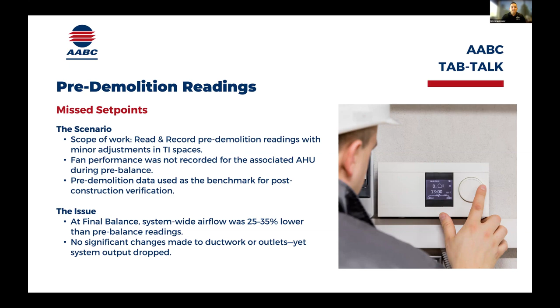This was kind of a follow-up to that, but we didn't have a baseline of the air handler, no RPMs or static to identify what it was doing at that time. So even though it looked like a simple read-and-record of the space, it turned into a bigger project, because now we're trying to reestablish the air handler's performance, looking at limited trend data from the hospital campus to figure out what that fan was doing prior.